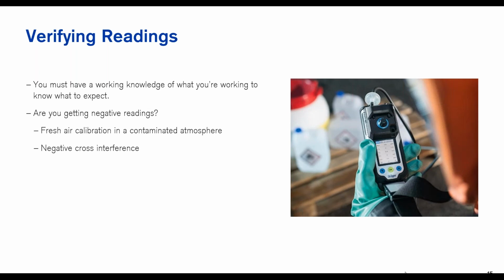There ended up being a problem with the type of meter they had. So what we ended up doing is I got a Dräger tube, took one designed for carbon dioxide, went out there and got a more accurate reading. So again, having those multiple methods and multiple avenues of figuring out how to verify that reading is crucial.